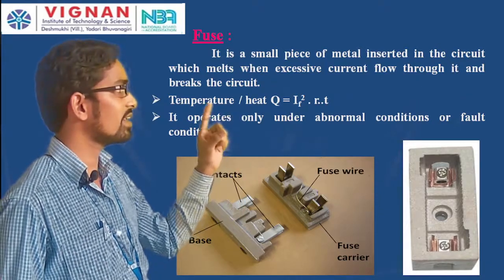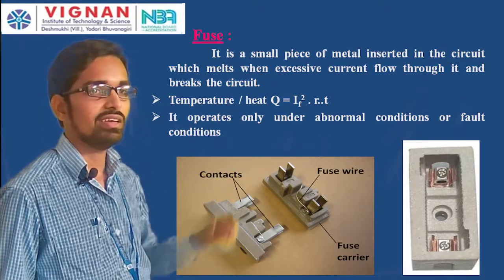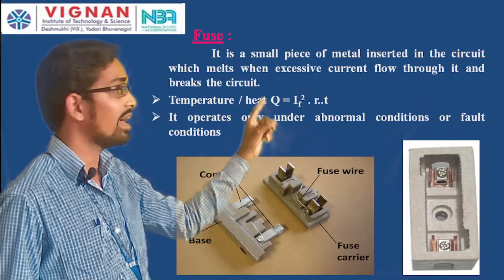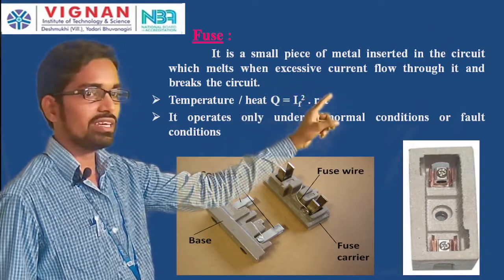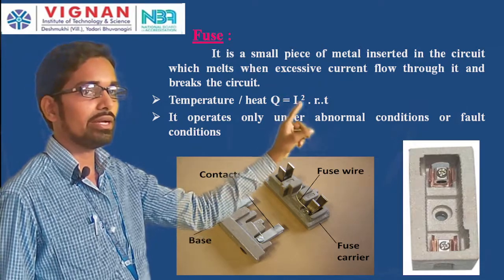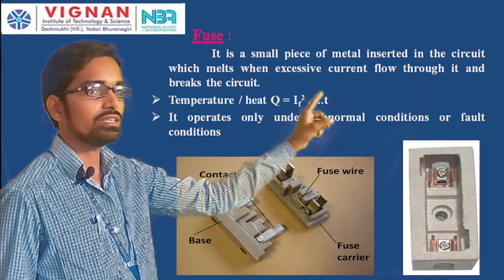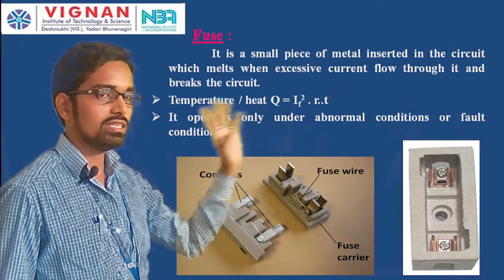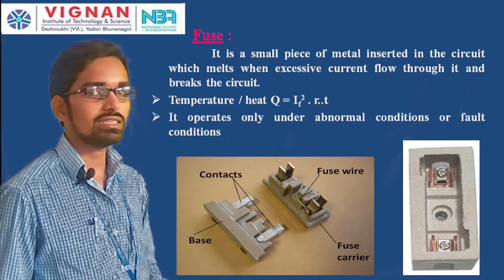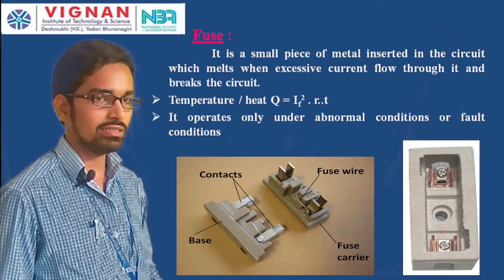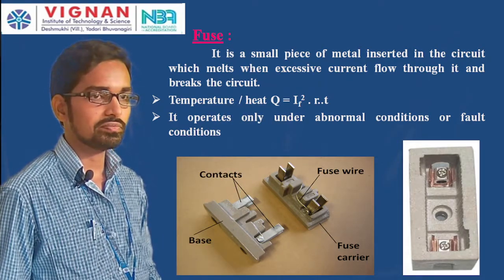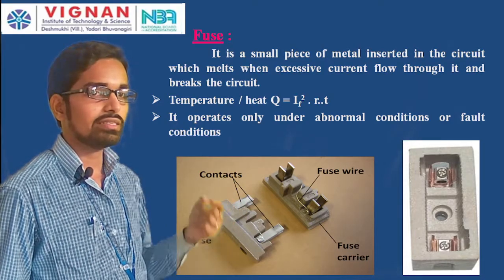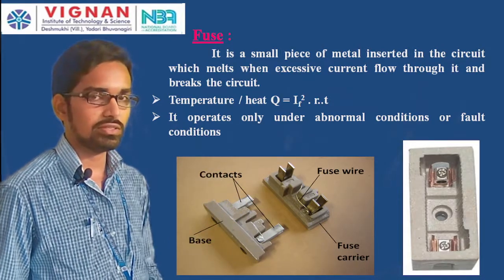The temperature or heat generated in a fuse is given by Q = I_f² × R × t, where I_f is the fault current, R is resistance, and t is time. When excessive current flows, this heat causes the fuse wire to melt.